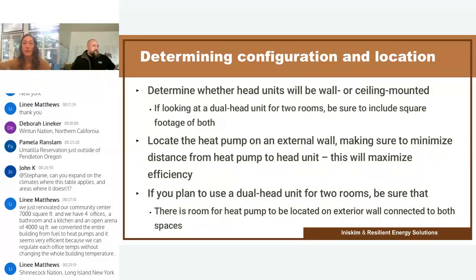And again, if you're going to use the dual head unit with the one heat pump, you want to pick two rooms that are adjacent and share the same external wall. That tends to be the smaller bedrooms in a home. If there are two bedrooms that are side by side, you can get the dual head units and one heat pump on the outside for those. So again, just be strategic about how you're placing those head units so that you can get the heat pump on the outside of that same wall and shorten that line between the two. Any questions there on locations or configurations?